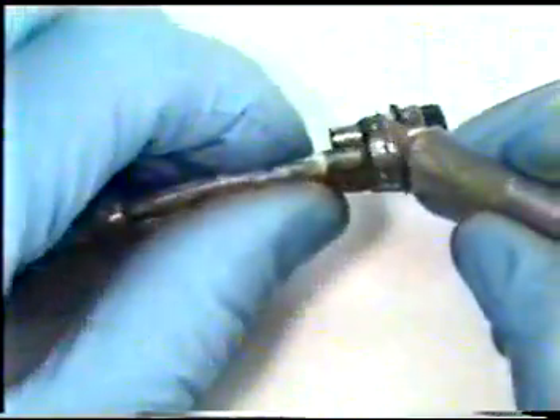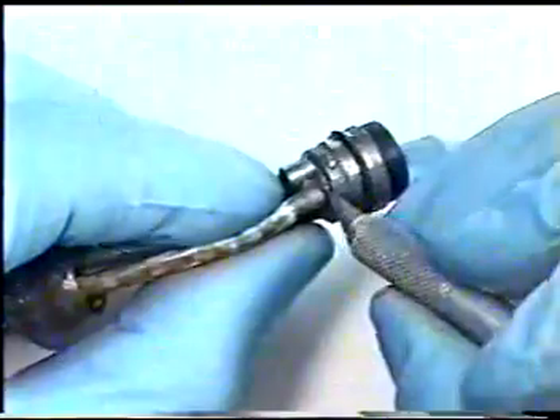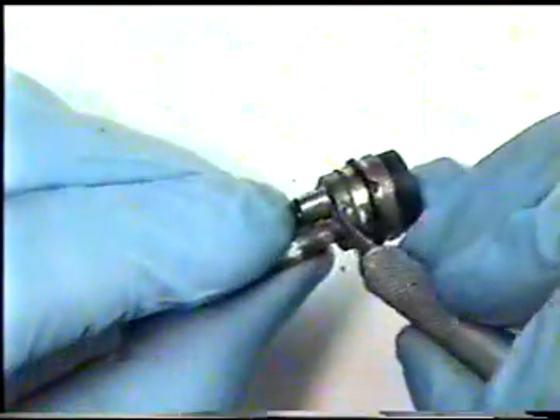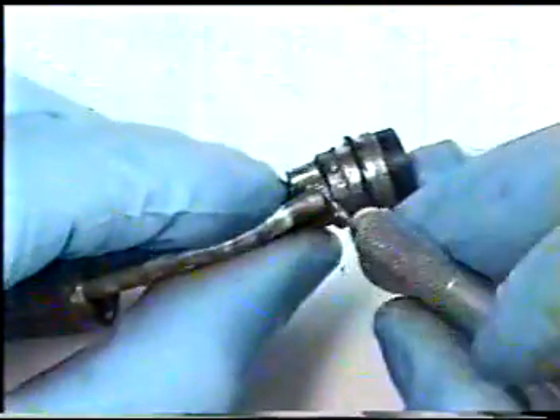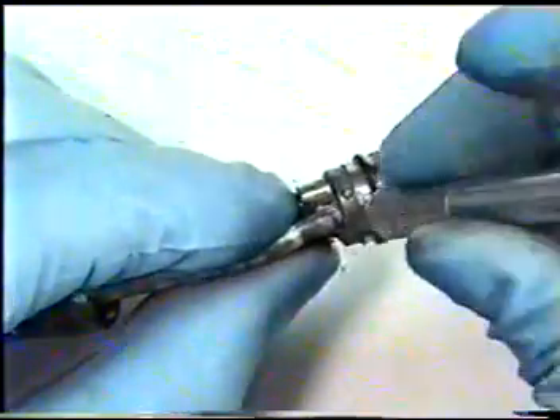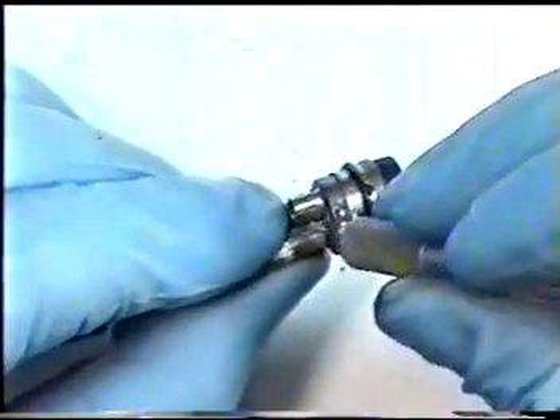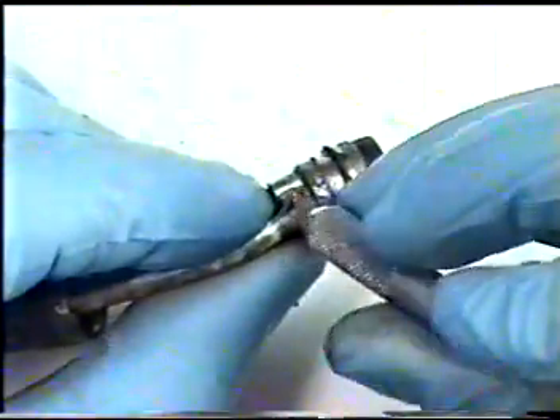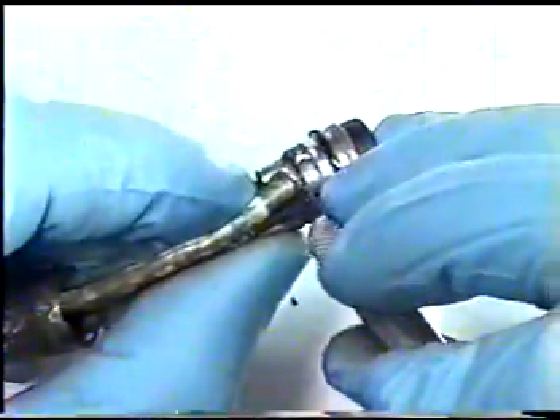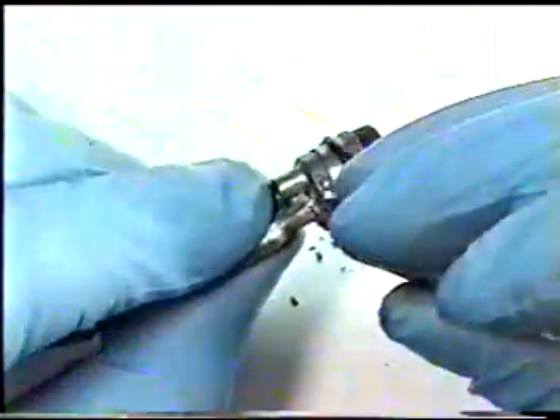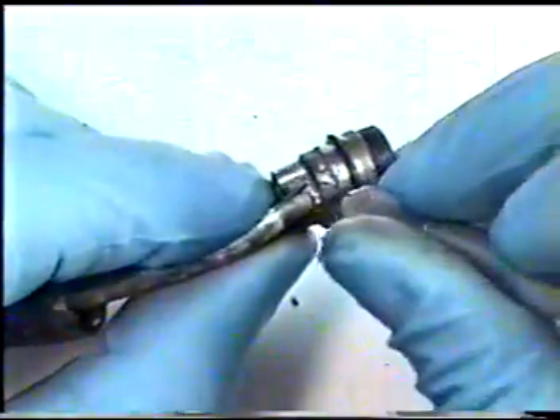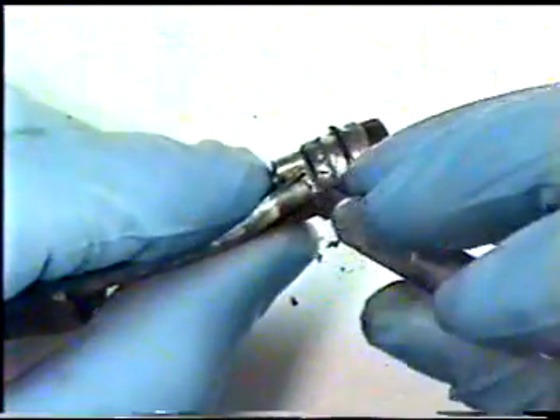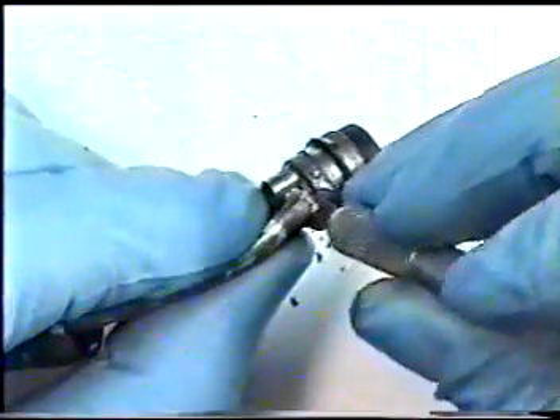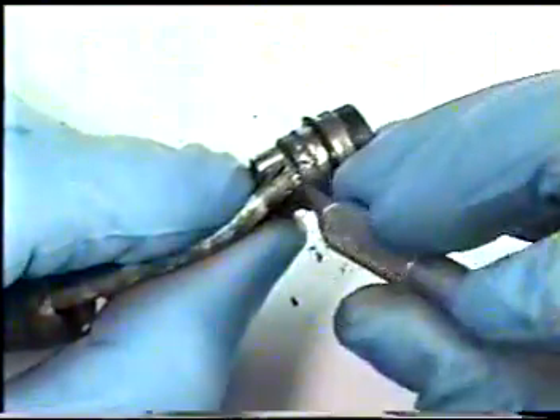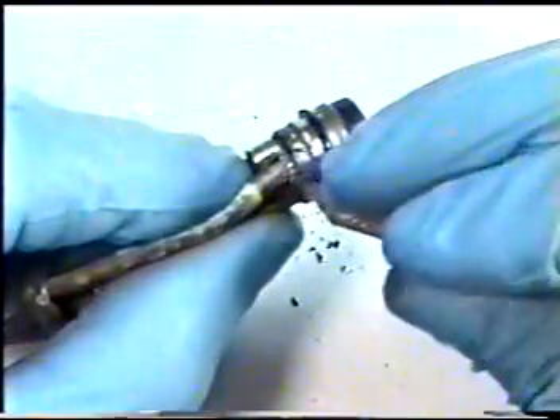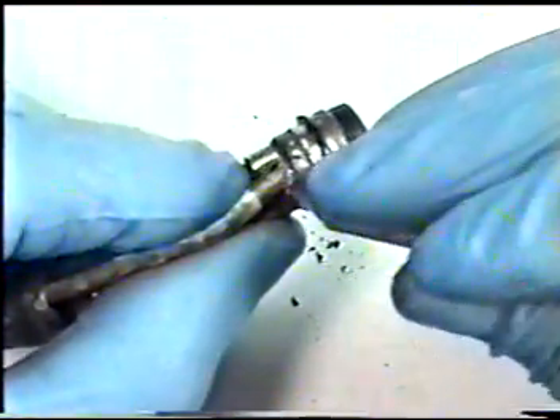Using a new sharp X-Acto blade knife, remove all the white glue which surrounds your damaged light guide bundle. Being careful not to cut into your image guide bundle or your CCD chip or your air water channels. Be sure to remove all glue from around your light guide illumination bundle post, otherwise it will be extremely difficult to remove light guide from the distal end. These are set at the factory and glued in very tightly in order to not be able to remove or replace them.